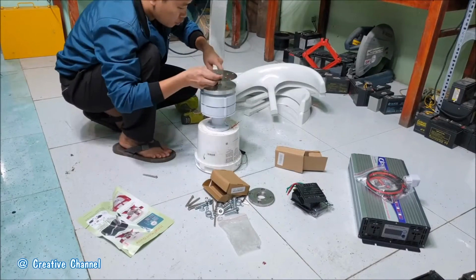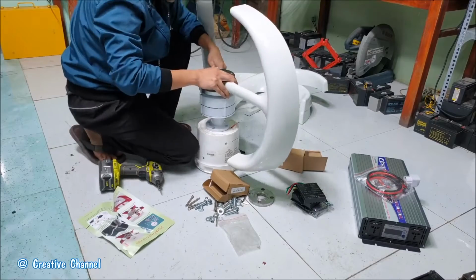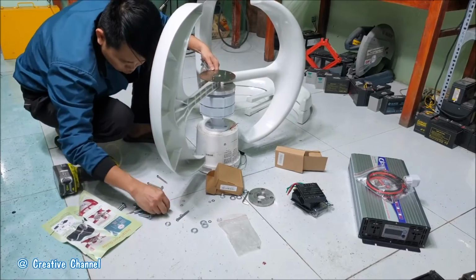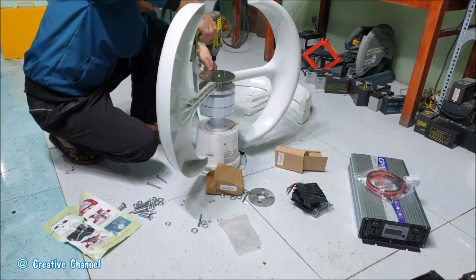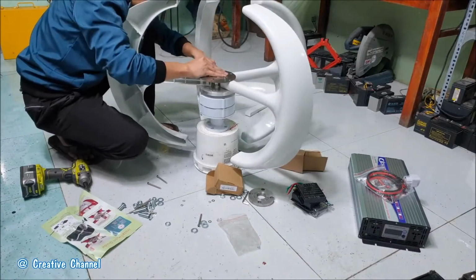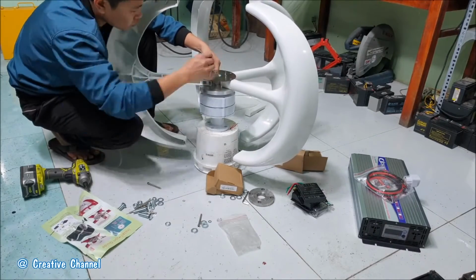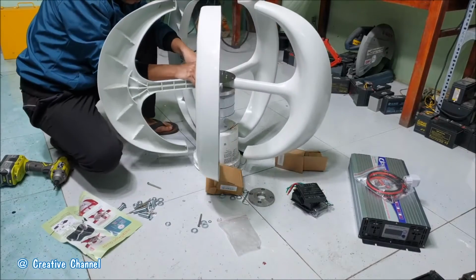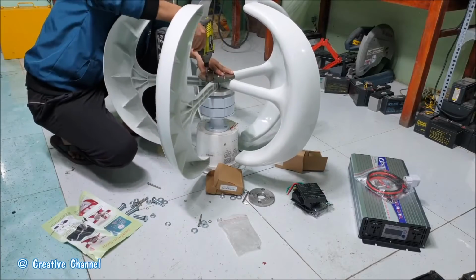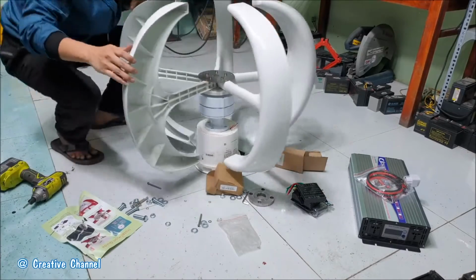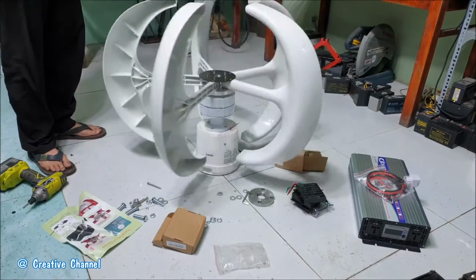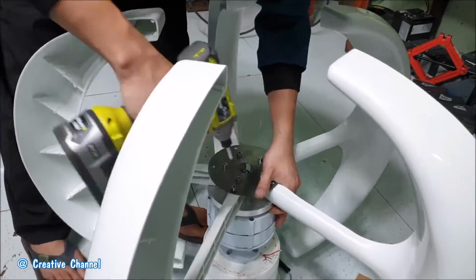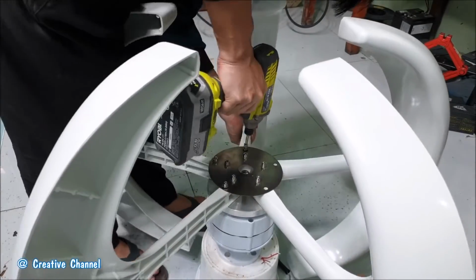And you may ask how the wind generators and the solar panels are protected. The protection of the wind generator is a dump load. When the controller finds the wind power or battery is full, or the voltage is too high or current is too high, the controller will stop the wind generator by dump load. It's a kind of short circuit, a kind of resistance. It will stop the wind generator at that moment. Or when the controller finds the battery is full or the solar input is too high, its protection is open circuit.